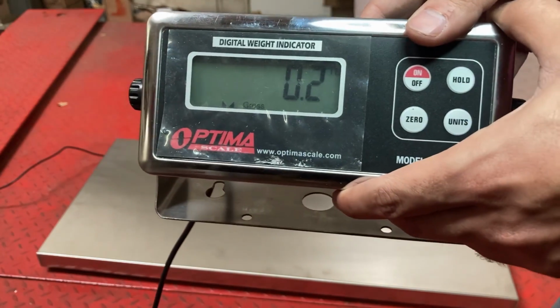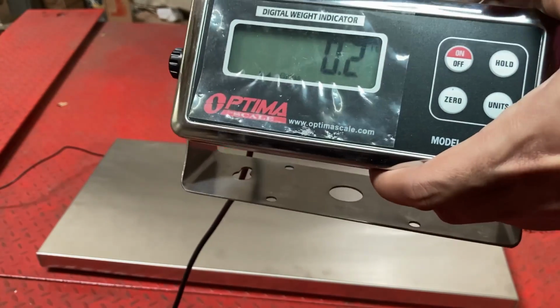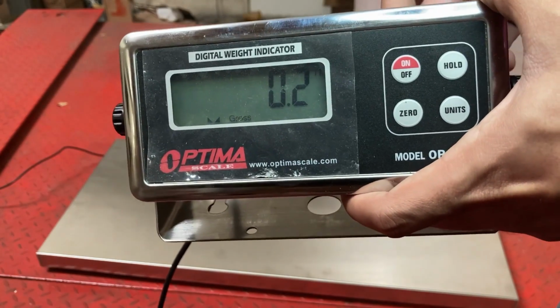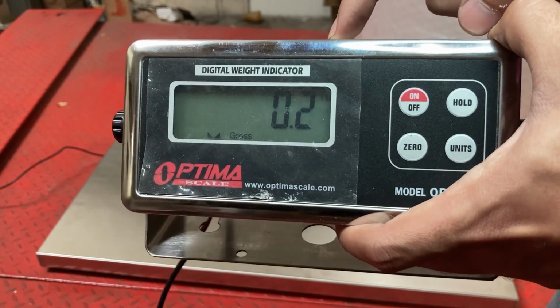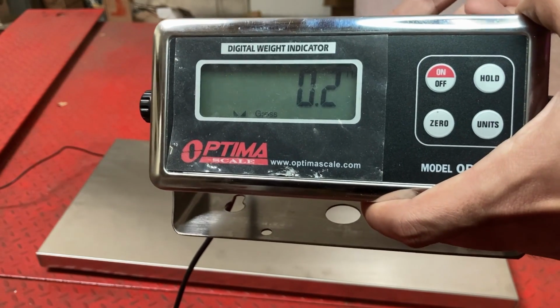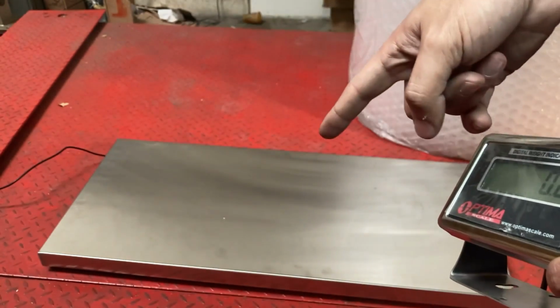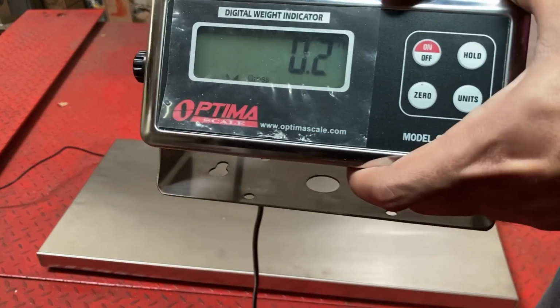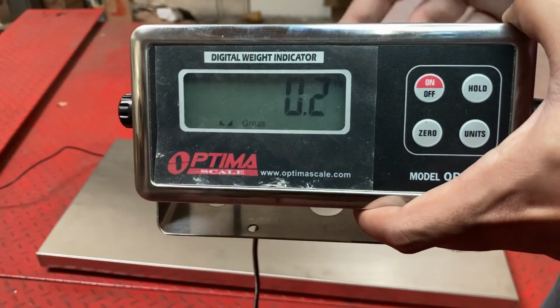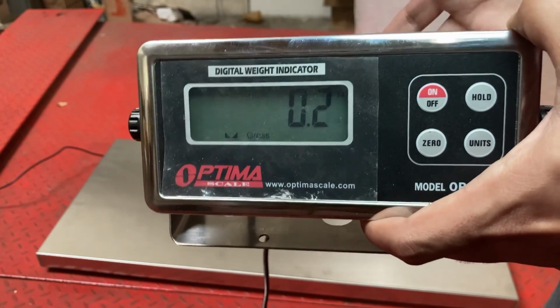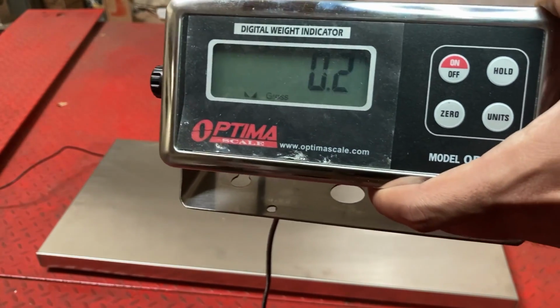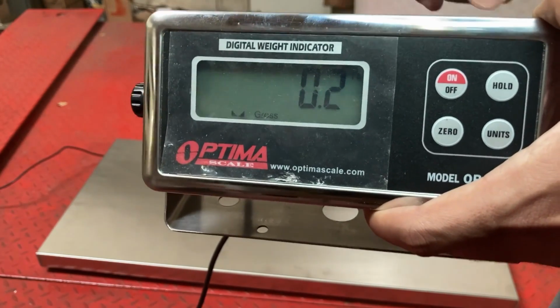It does happen every once in a while, especially after a couple years of usage, but there's not much you could do about it. There's no repairing it, and we don't have boards or parts for these. Your vet scale is fine, the platform at least, it's just that the indicator might not be reading at all. If it's reading something, it works. So either it works or it doesn't. If it doesn't turn on, or it's having issues, it means the indicator needs to be replaced.